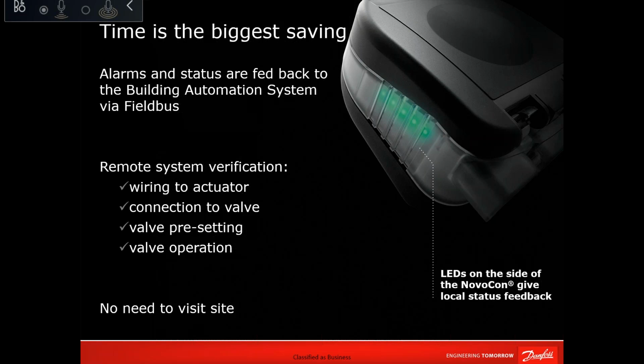Why I spoke about the EC fan motor is because the output from Novocon is 0 to 10 volt. This output can be linked with the sequence of operation, which means I can tell the Novocon to make this 0 to 10 volt, make it 5, if the temperature on PT1002, the temperature sensor 2, is going 22. So I will reduce the speed. What makes me do this is the sequence of operation that I want to achieve by removing the controller and using an EC fan motor. So that's why I was saying only EC fan motor.